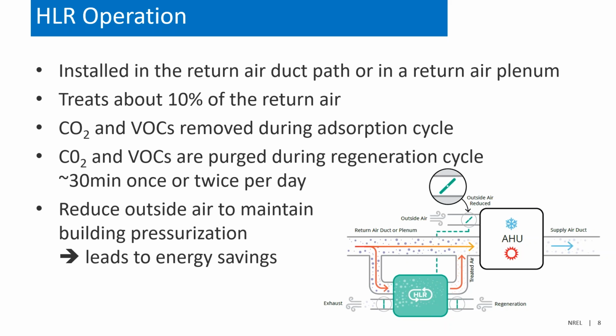And then, as I said, during the adsorption cycle, it removes the CO2 and VOCs. And then once or twice a day, depending on the level of pollutants and the number of hours of operation, you have to go through a regeneration cycle, which takes about 30 minutes, but it can vary depending on how many contaminants you want to purge. And you do that maybe at night time or during periods of low occupancy. And then when the HLR is on and you can clean out the inside air, that allows you to reduce your outside air in the building, which leads to energy savings, because now you don't have to condition that air, to either cool it down or heat it up depending on the time of year.